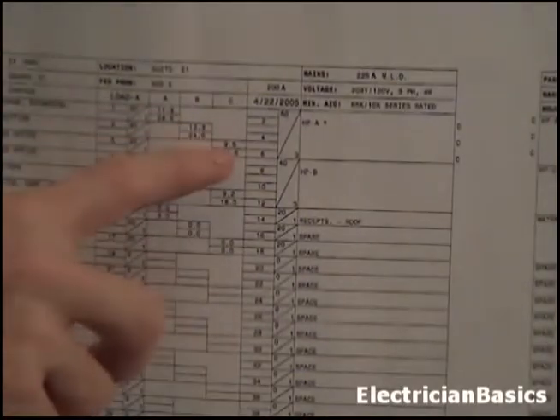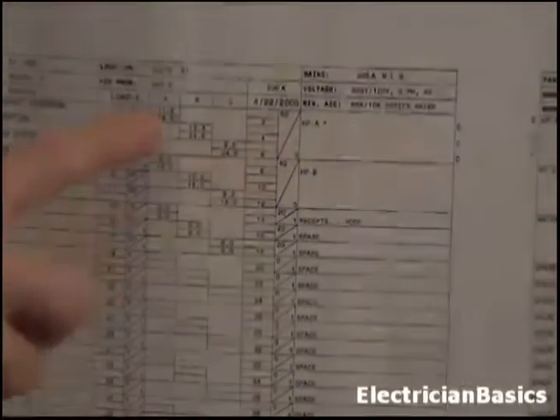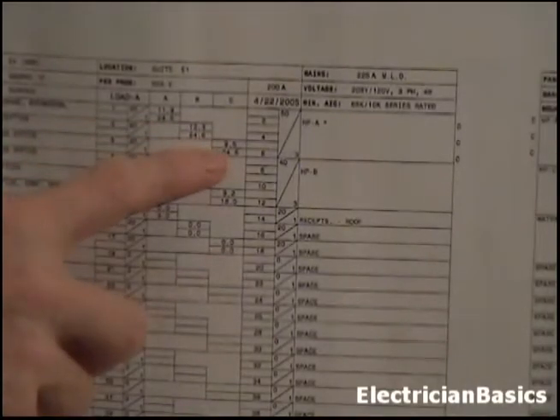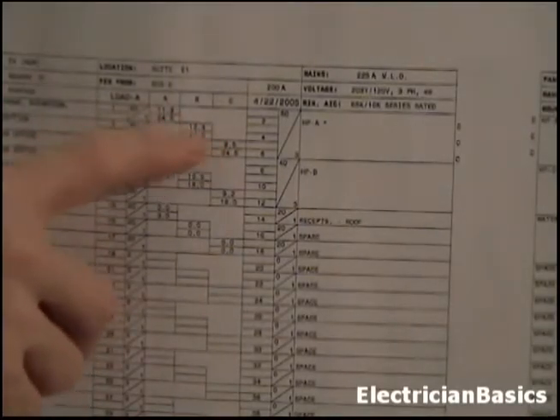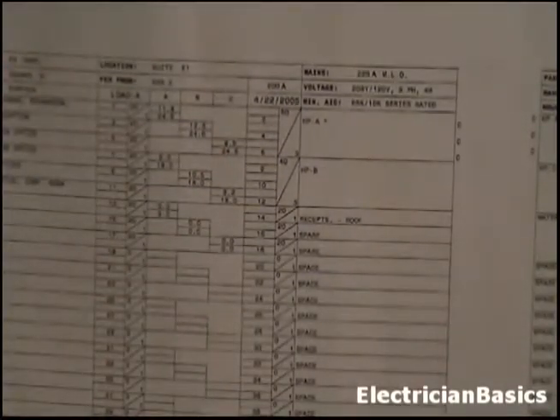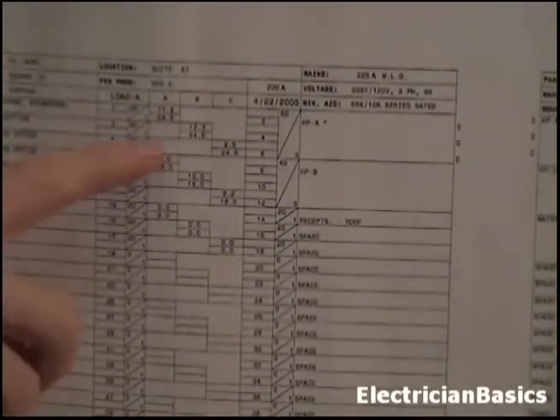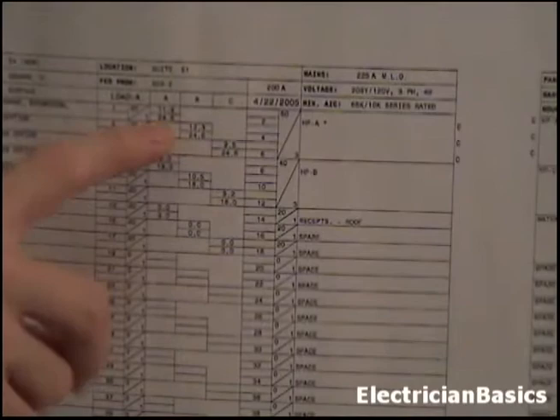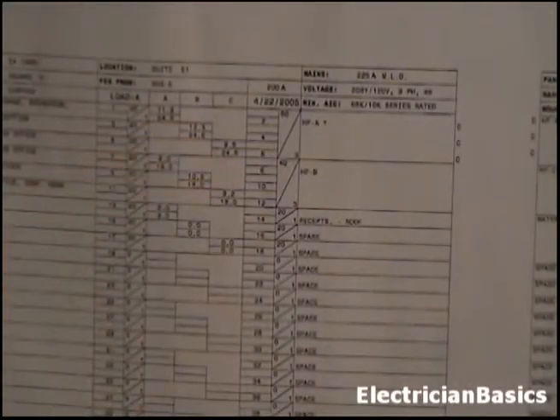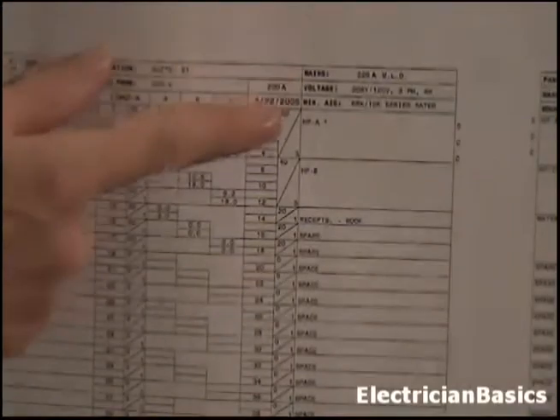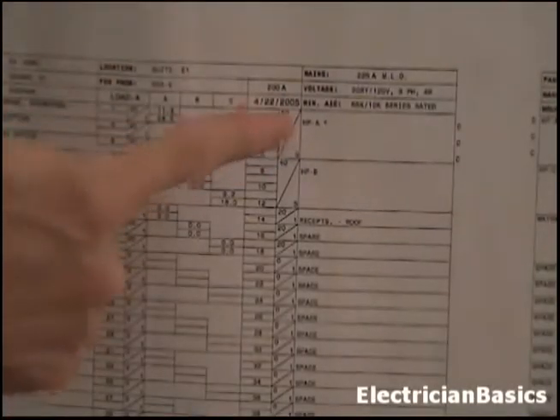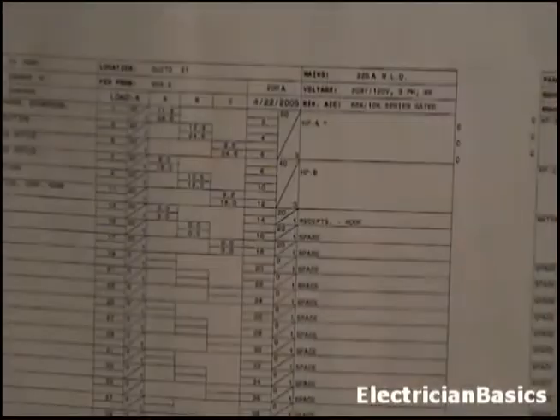Now the top number, again, the odd number is going to be on the lights. And you can see all these even numbers, 24.6 on each one on the right side. And the reason, now the ones on the lighting, you can see they're different. That means there's different numbers of lights. It's drawing a different amount of power on each circuit. For the heat pump, all 3 of the phases will be drawing the same amount of power. That's why they all say 24.6. So remember, when you have this diagonal, that means it's going to take these 3 spaces up with that one single breaker.